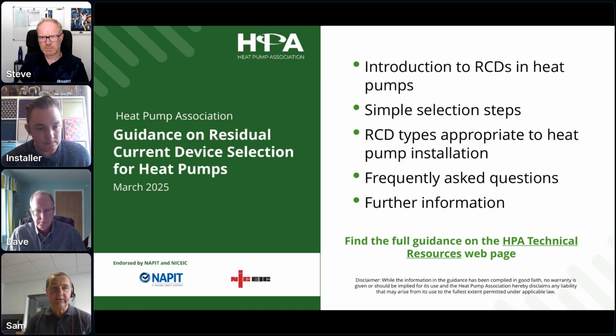First of all, make sure that you select the RCD with the correct nominal rating so that it's not going to trip under normal circumstances. And secondly, also select the RCD that operates correctly with the DC leakage current, which is there under normal circumstances. If you don't do either of those selections, then it can result in nuisance tripping, which means your RCD will trip in normal circumstances, and you're going to lose supply, which in the case of our heat pump means we're going to lose that heat generation, and unless we've got a backup system, there's going to be no hot water within the installation.